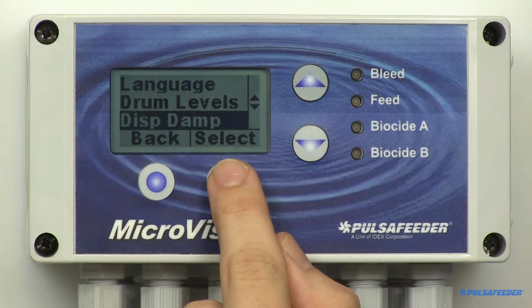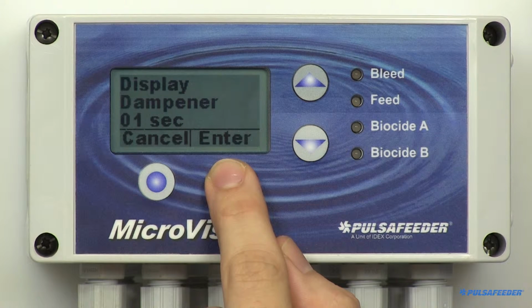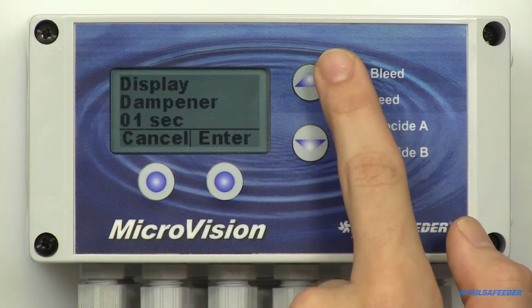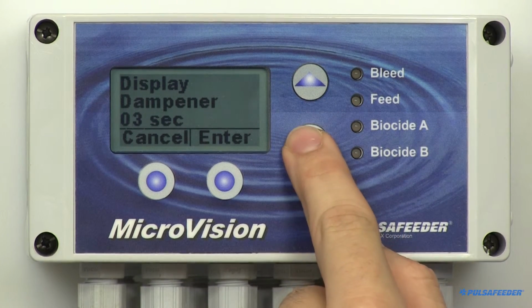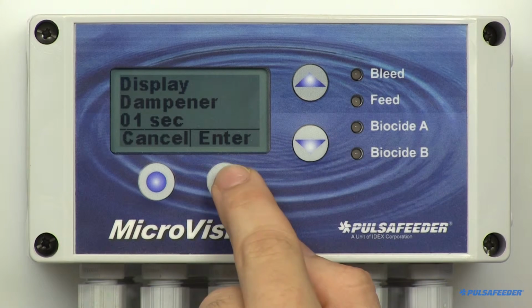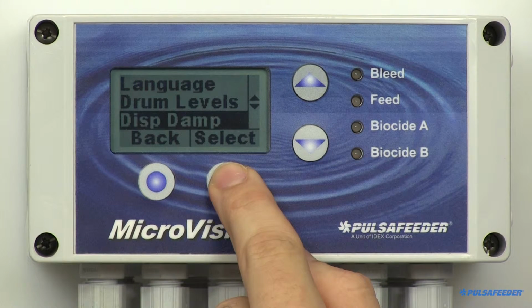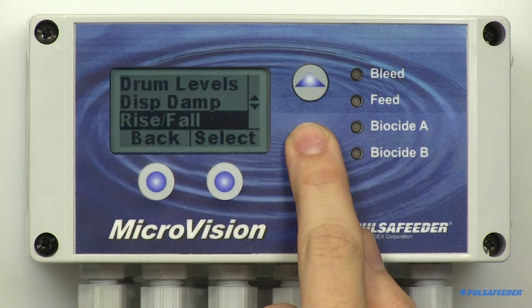The next section in the Configure menu is the Display Dampener. This setting allows you to select how often the actual conductivity reading is updated on the home screen, but it also dampens the controller's response to sudden changes in conductivity. To access the Display Dampener from the Configure screen, find and select it. You can increase the number of seconds using the arrow buttons. The controller takes a conductivity reading every second, and this value causes the controller to average the readings, hence slowing down the control functions.